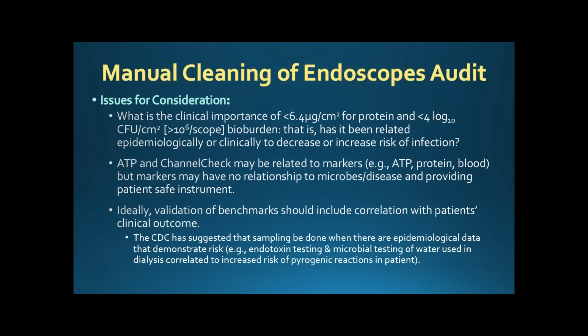So you have that. And then you should only ever do environmental sampling if you see that there's a potential risk. That's per CDC suggestion. So, scope storage. We want to make sure that it's a closed, locked cabinet that doesn't touch the sides, things like that. If you can have it HEPA filtered, that provides that pressure.